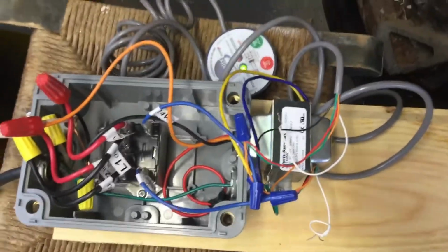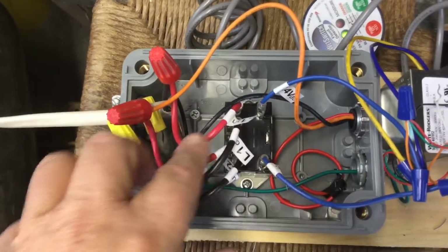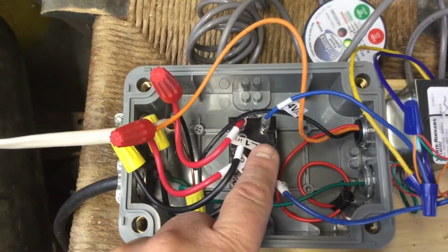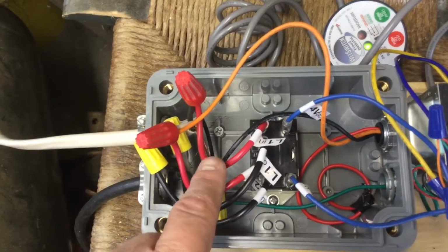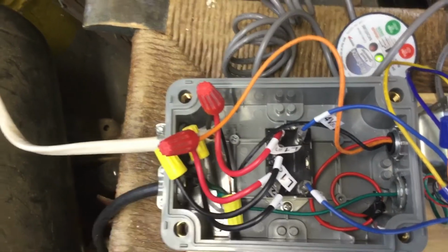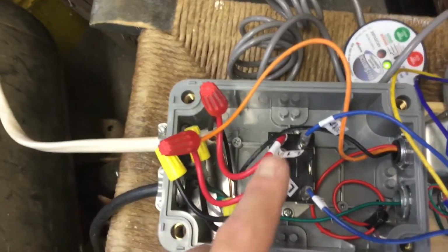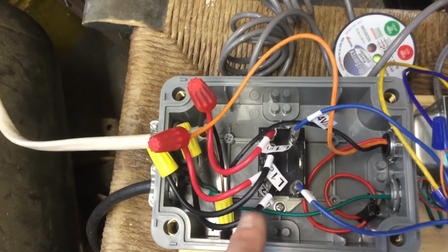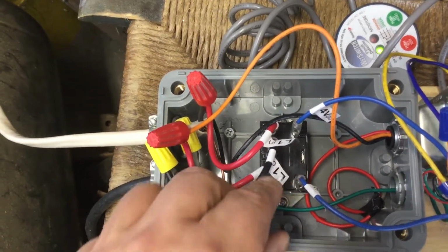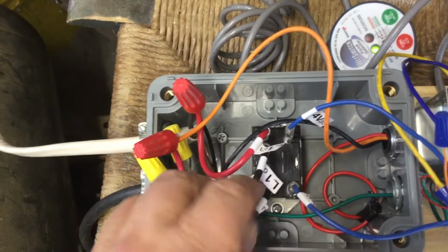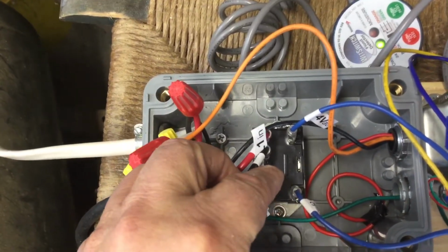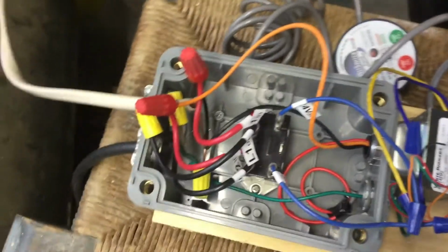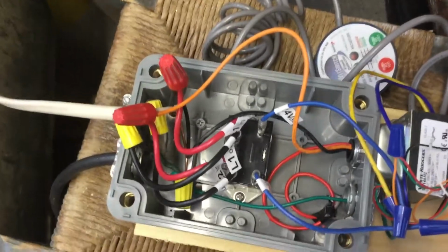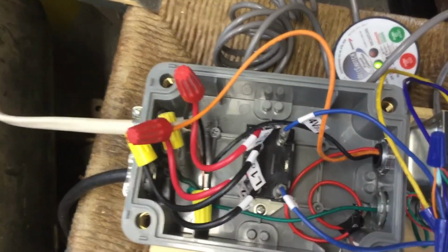It looks complicated, but it really isn't. If you look at the pump relay, the red lines are line in. My pump is 220, so the red are the 220 lines, power coming from the fuse box in here. The black L1 out are the lines going to the well pump. So that's the wiring. Obviously there's a ground wire.